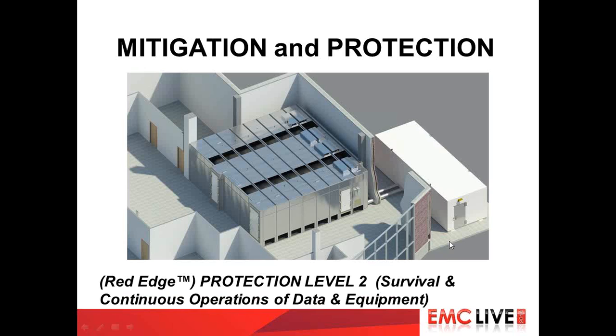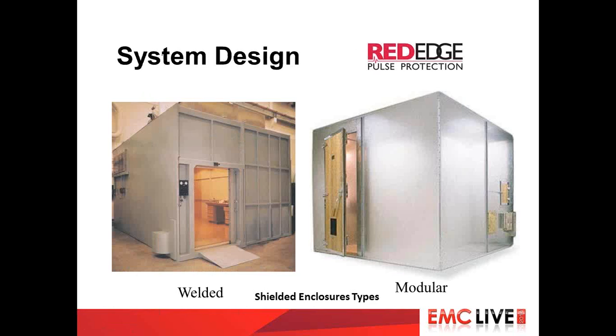And this is an example of that same protected environment within the data center facility, although you do see that it's connected to an outdoor facility that would house the generator and the cooling towers and chillers for the cooling systems. These are photographs of some of the basic shielded enclosure designs. To the left, we see the welded enclosure, and that's made up of a steel plate, minimum of 3/16 inch thick and sometimes thicker, with continuous seam welding in all directions. On the right, we look at a modular system, and this is a bolt-together modular system that is brought to the site and assembled in place.